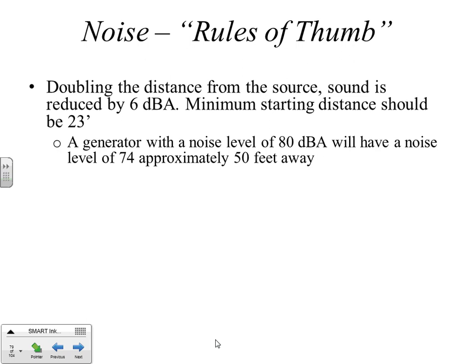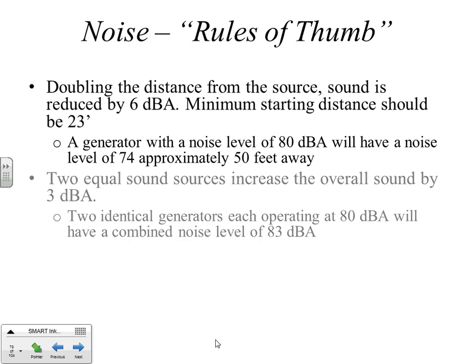And it's an exponential scale. That's why these rules will work. Two equal sound sources increase the overall sound by 3 dBA. So two at 80 will be an overall combined noise level of 83. You would think they will double the noise. Yeah. A lot of people would think two generators will double the noise.